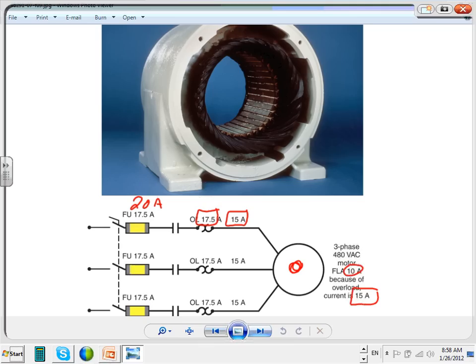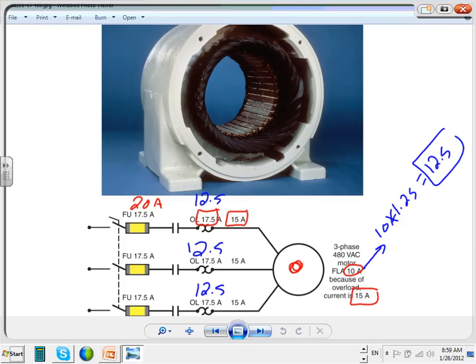Until it burns itself, if you put the overload protection at 17 and a half. But remember, the overload protection was supposed to have been sized at what? 12 and a half. If you size it based on the code at 12 and a half, as it should have been, instead of 17 and a half, and you're pulling 15, what's going to happen to the overload? It's going to open, and it's going to save you $300-400 buying a new motor. Any questions, guys? If you look at these pictures, the inside of it is completely burned because of overload. That's why we have the overload, and that's why they don't want you to go higher than 12.5. This should have been 1.25 times 10, right? Based on the code, you take the 10, multiply by 1.25, and that gets you 12.5, and then you set the overload at 12.5.